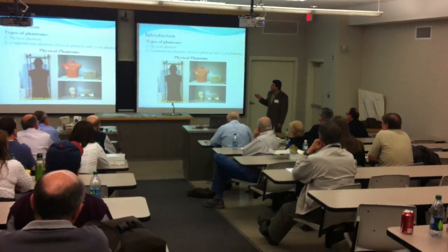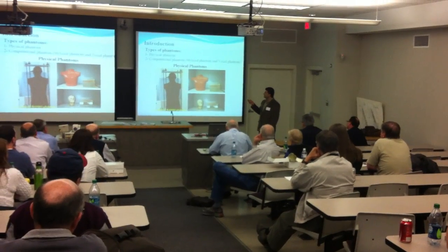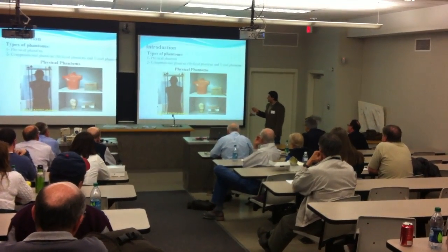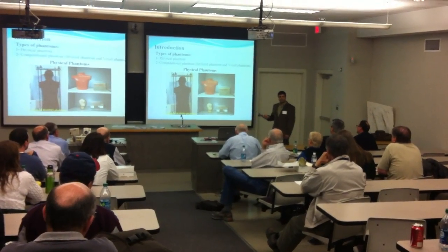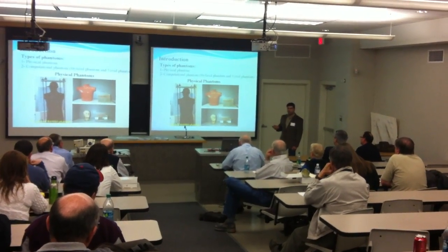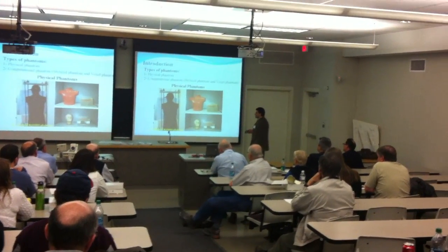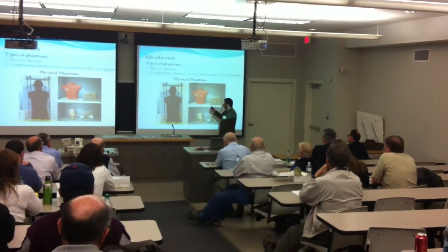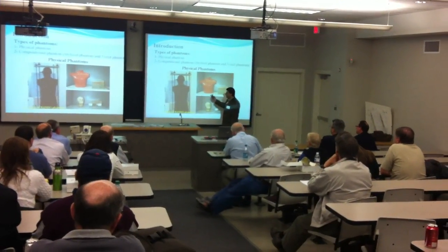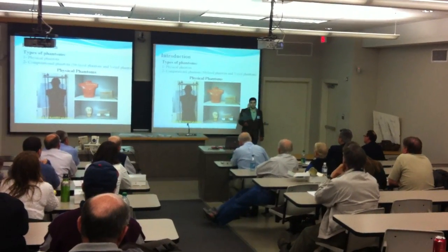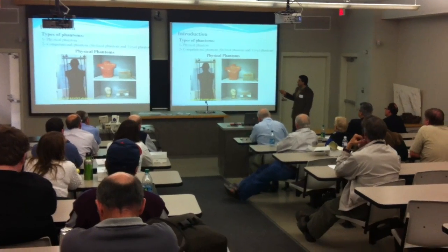Two types of phantoms are usually used for efficiency calibration: physical phantoms and computational phantoms. Physical phantoms capable of representing the human body have been used for efficiency calibration since 1950, and the classical method applied for efficiency calibration is performed with physical phantoms that are loaded with radioactive materials in the region of interest to relate measured counts to radionuclide body burden for a given geometry.